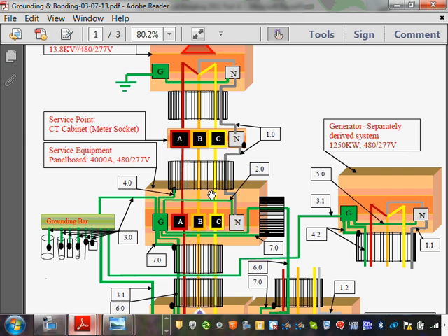If you're a house, if you're a smaller building, and in residential, it's not a concrete building, no concrete encased electrodes, so you typically have to drive a ground rod. In 2011, you have to supplement it with another ground rod because we don't trust ground rods by themselves. And you also have to tie to the water. That was a change in 2011. So you have to have 2 ground rods and a water pipe if you are doing ground rods and water pipe.